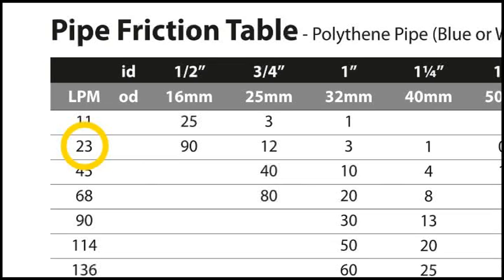If we keep the flow rate the same, but double the pipe diameter to 1 inch, friction loss reduces to only 3 metres. That's a huge difference!